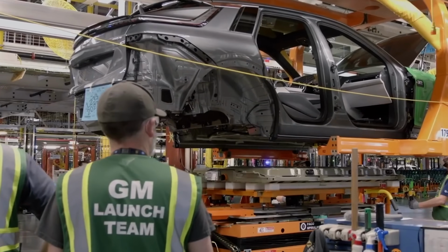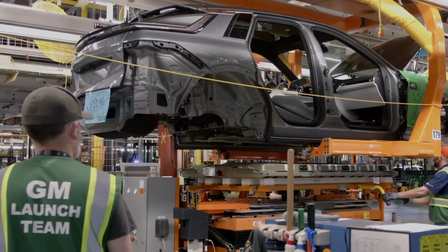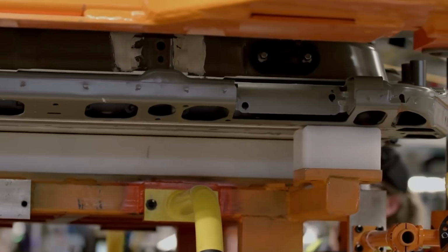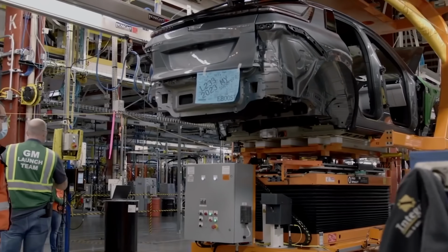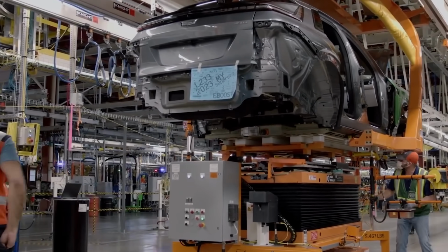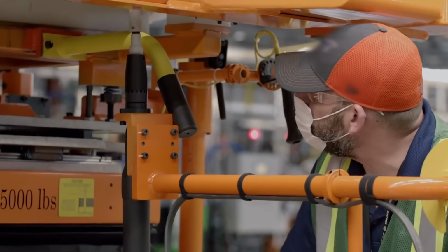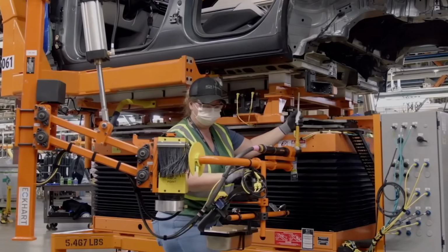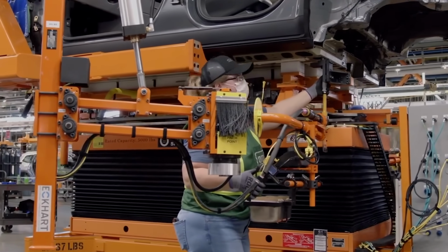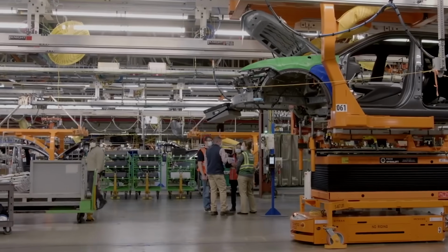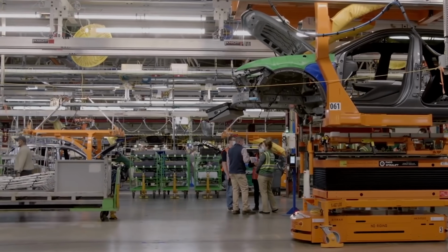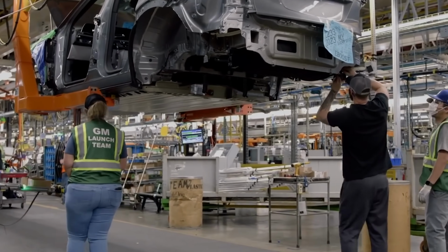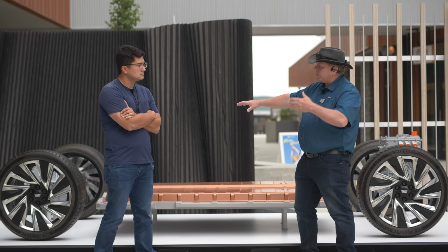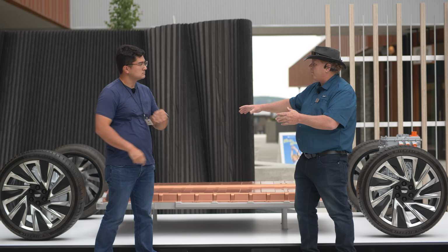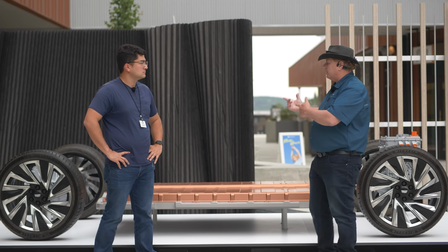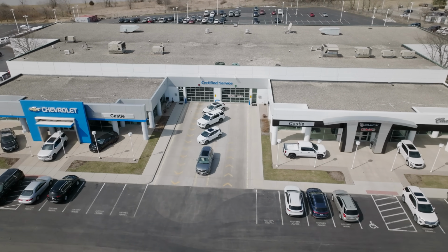To make that happen you need the heat pump, but also a control system to manage it. A common issue with heat pumps is their coefficient of performance drops way down in the cold. So you put the drive unit on the same loop and use its waste heat to precondition that loop, getting it to a very efficient point for the heat pump, instead of dumping that heat overboard through a liquid-to-air heat exchanger. That makes the heat pump more efficient and helps manage the cabin.